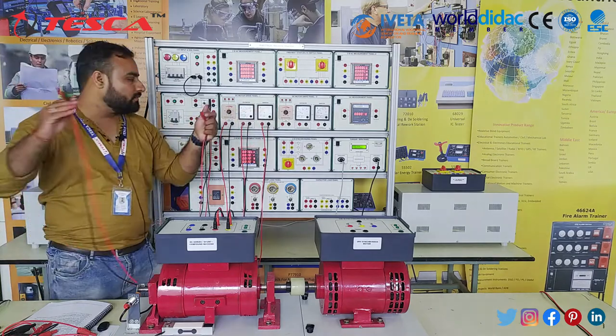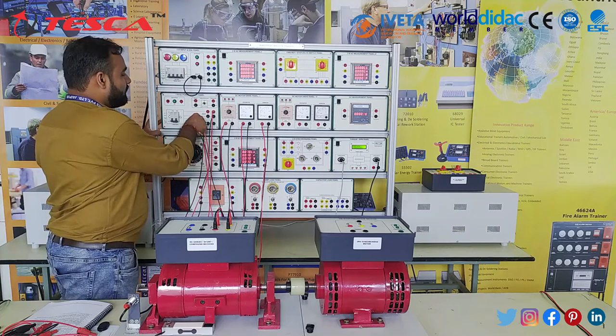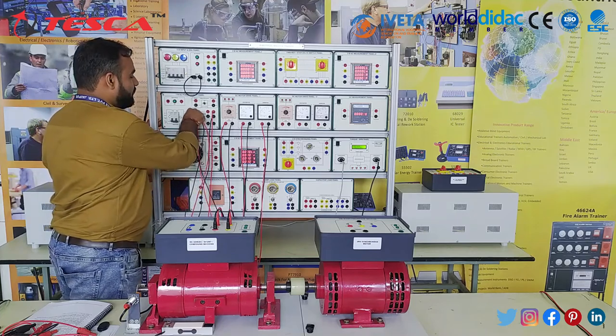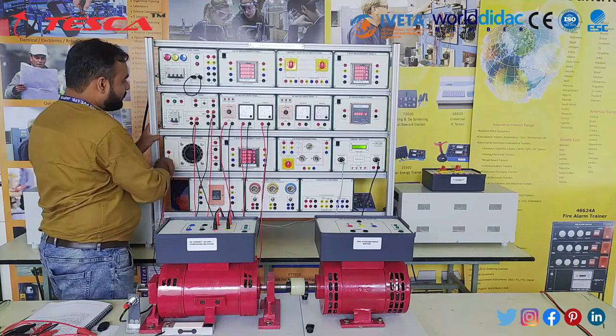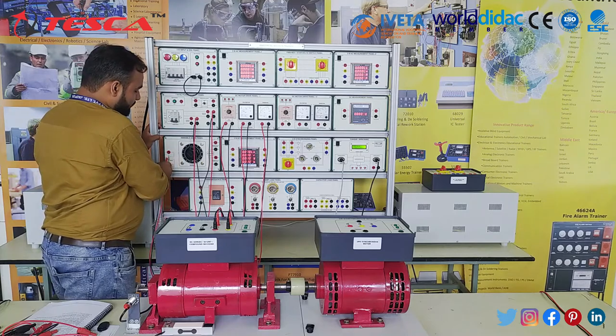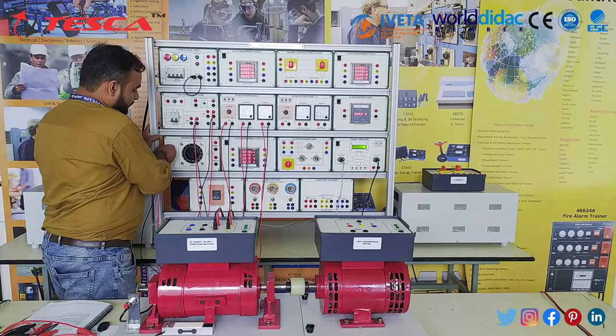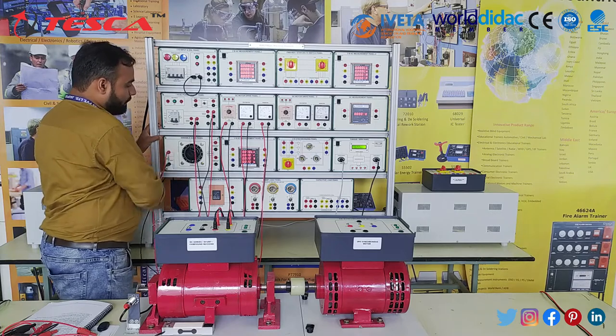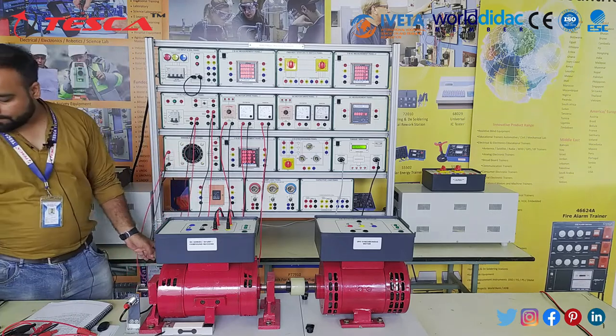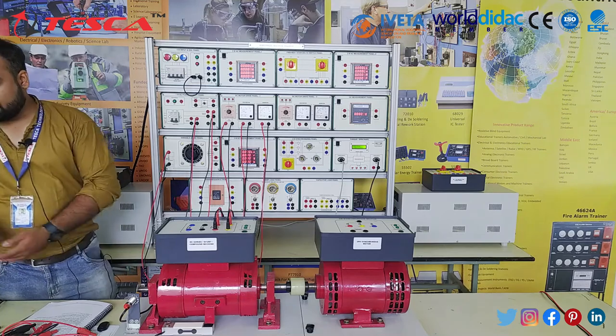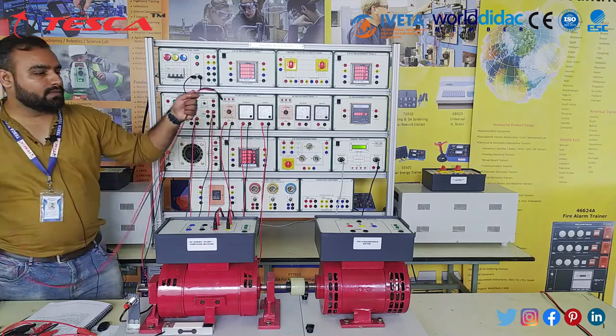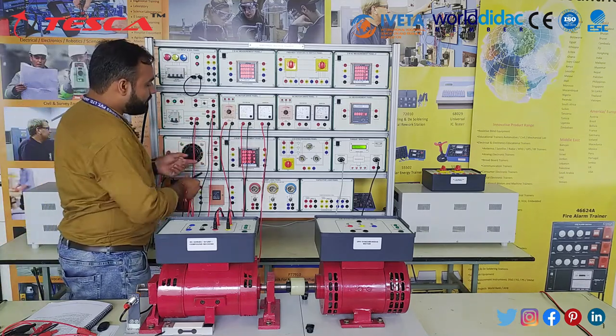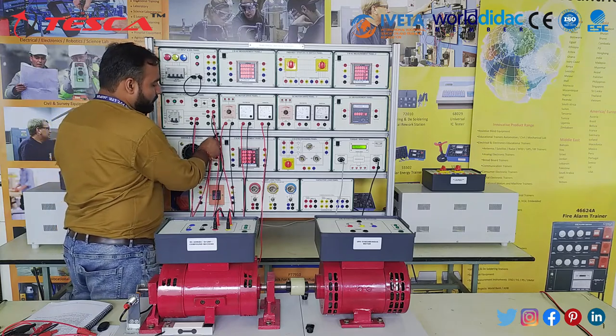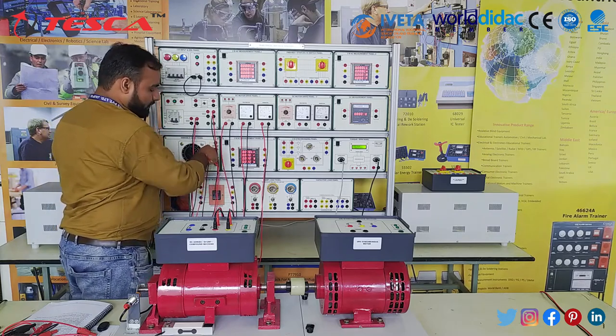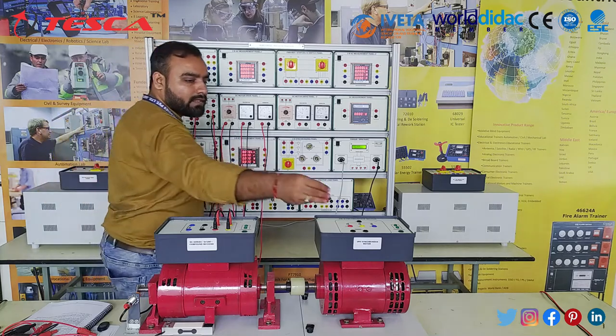For this, we will connect T4, T2 from the AC measurement panel to T2 and T1 respectively on the variable AC DC panel. Now from here, we'll use the DC rectified output, variable output of DC, to the field coil of the synchronous generator.